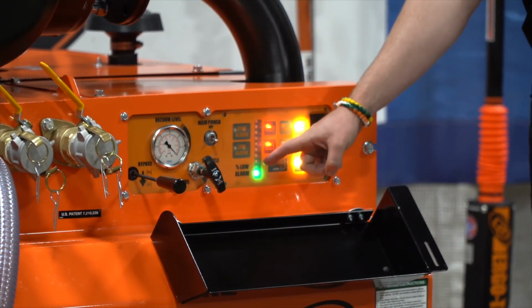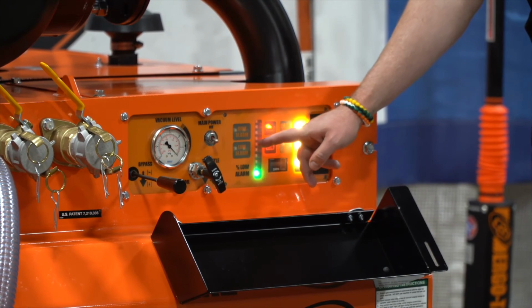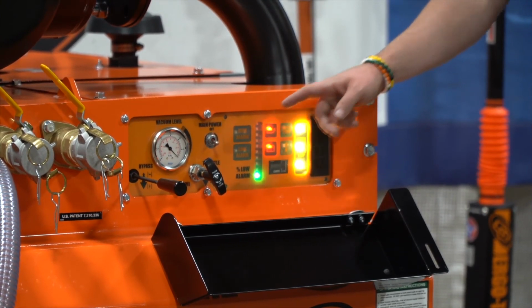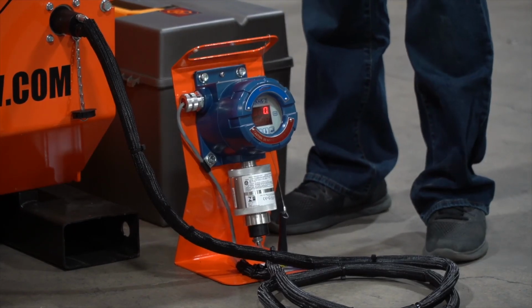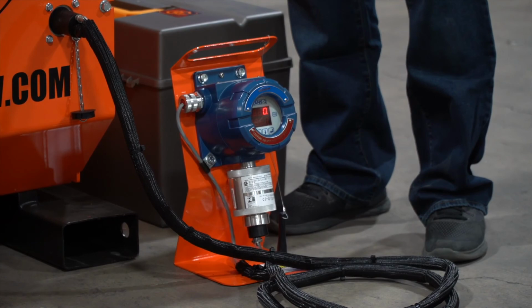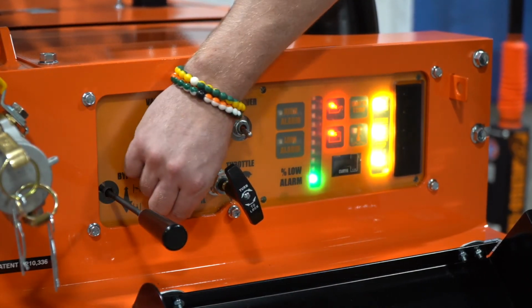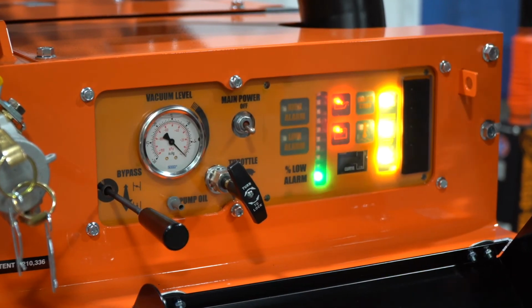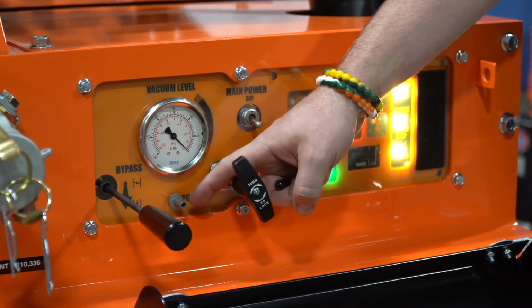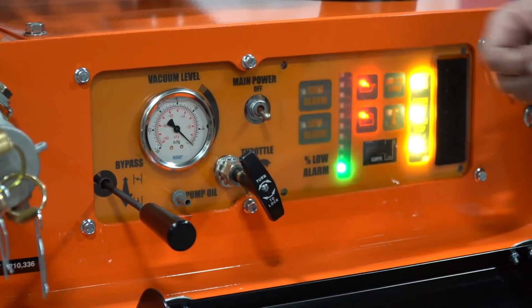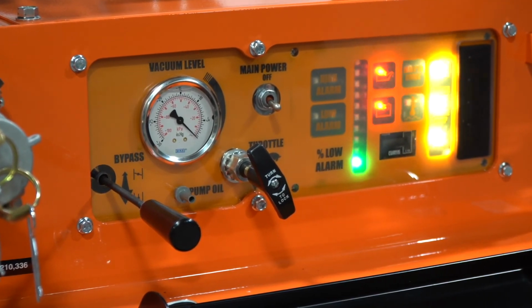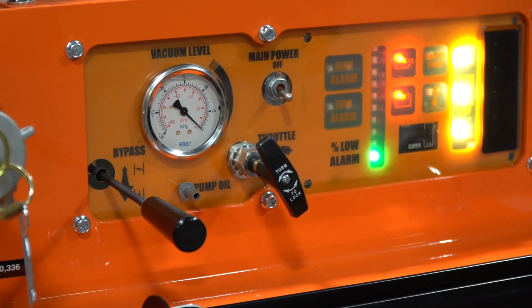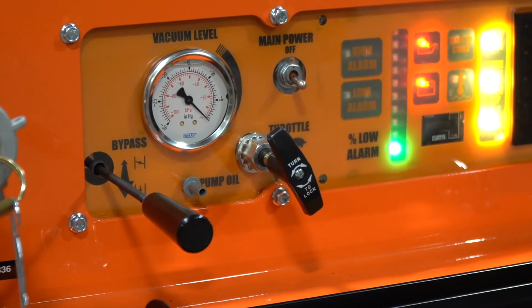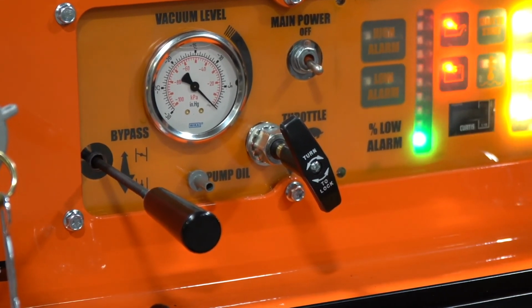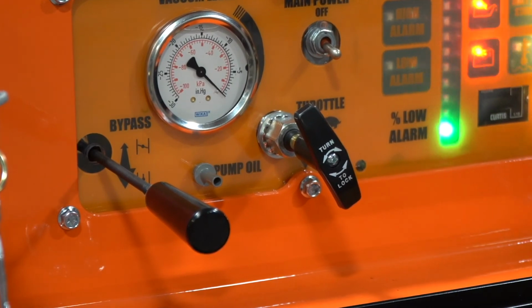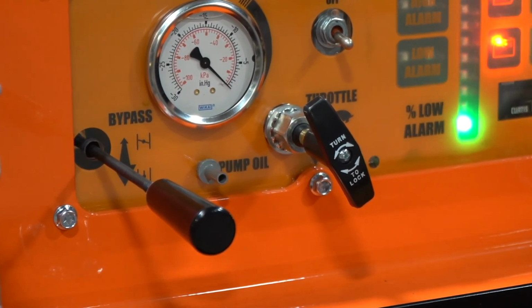Now as you're running the unit, you'll see green, yellow, and red lights that correlate to what is going on within the unit to this sensor here. Now I'd like to talk about the pump oil spot right here. This is where you will put WD-40 or any approved substance into here to lubricate the blower. By lubricating the blower, it'll ensure that the blower itself will have a longer lifespan, as well as the coupler will last longer.